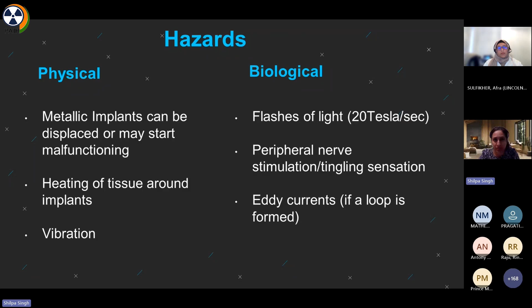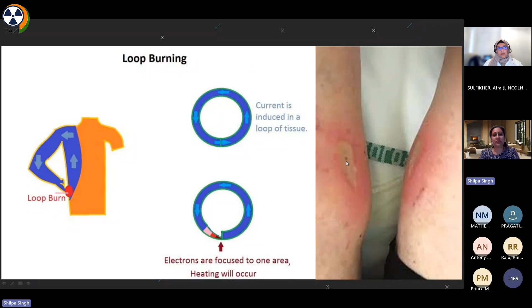Eddy currents. Eddy currents are some extra currents which can be induced in the patient's body. They are induced because it forms a loop inside the patient's body. What is that? I'll show you an example. If you see, the patient's hand is kept on the waist, and it converts the patient's body part into a loop, and this loop allows the eddy current to flow into the body. Of course, it's not good.